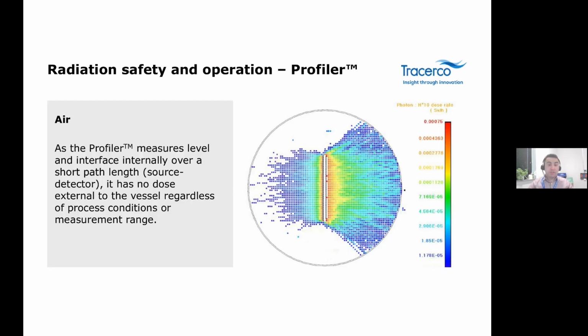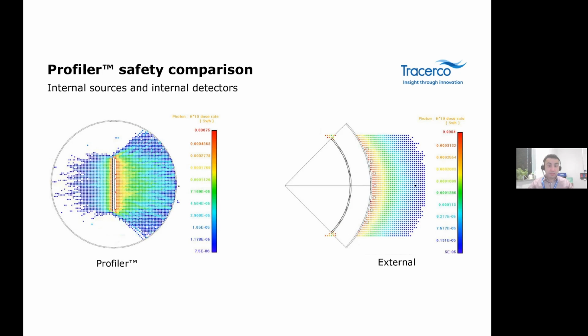I'm going to briefly talk about the safety aspects as well, and as Oliver said, about the conventional instruments and the radiation profiling. This is our study. You can see it measures internally with a short source detector and passes as a profiler, ensuring no external radiation exposure, regardless of process condition or the measurement range. And we're just going to compare two of them.